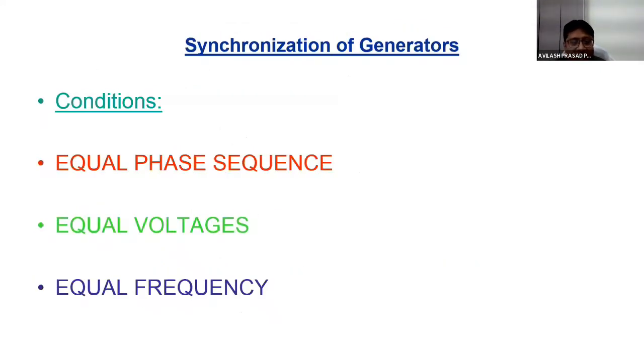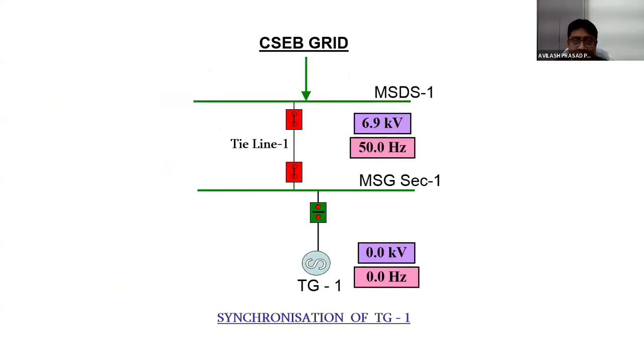Synchronization of the generator. The conditions, again, as we have studied in the book, are equal phase sequence, equal voltage, and equal frequency. Now it is shown through the diagram. The first is the CSEB grid, which is connected with the MSDS1, whose voltage is 6.9 kV and frequency 50 Hz. And our MSG is the main synchronizing generator section 1, where if the TG1 is not operating, then it is 0 kV and 0 Hz. If it starts rotating at 48 Hz, and if we give excitation and increase the excitation, 1 kV, 2 kV, 3, 4, 5, 6.